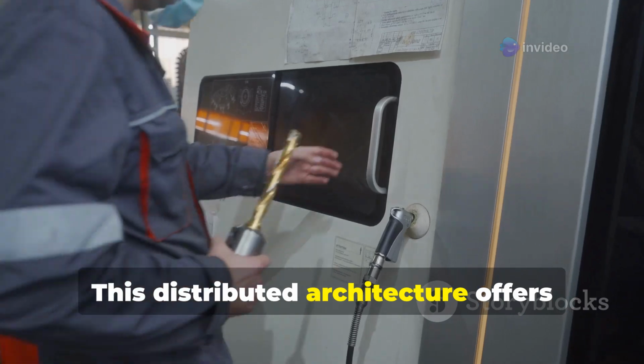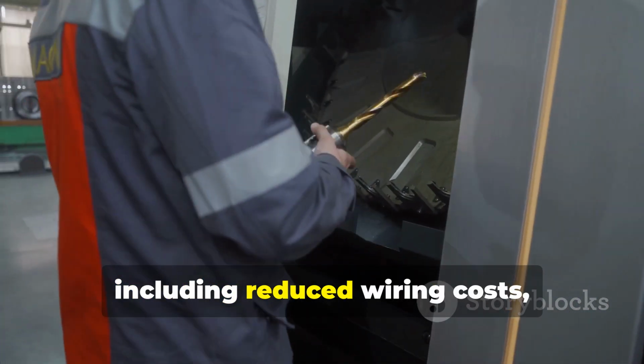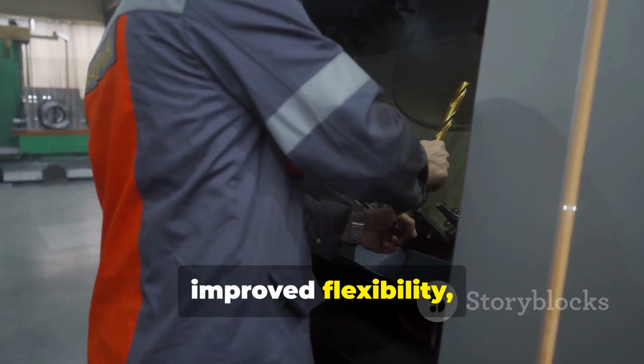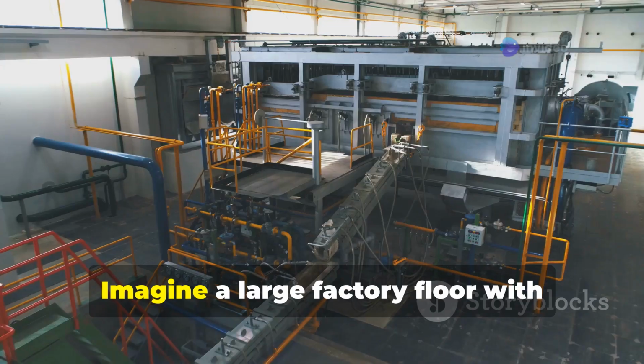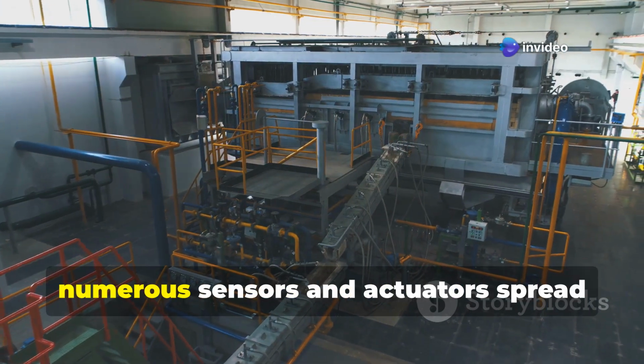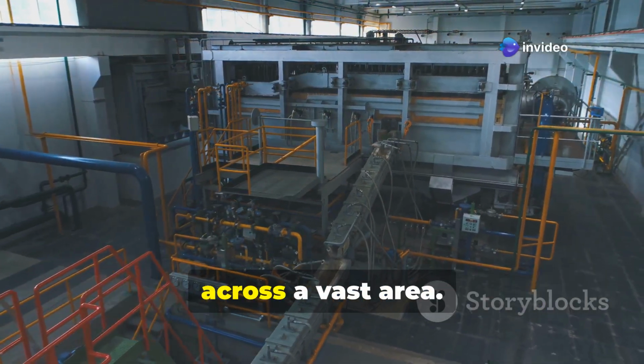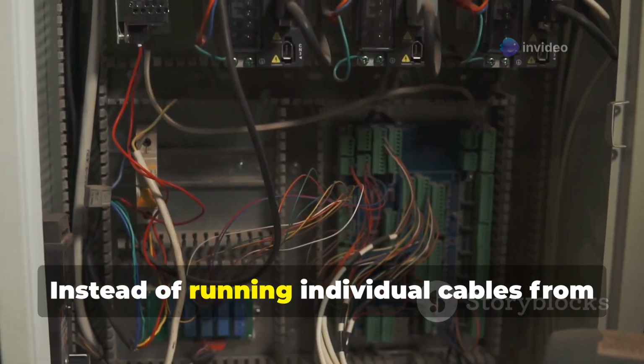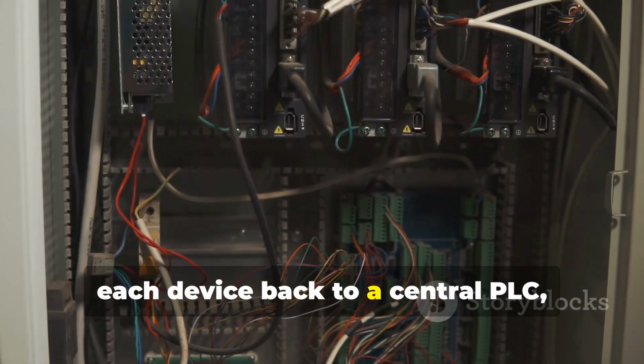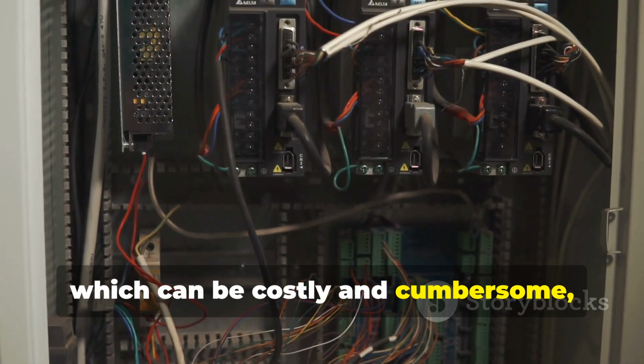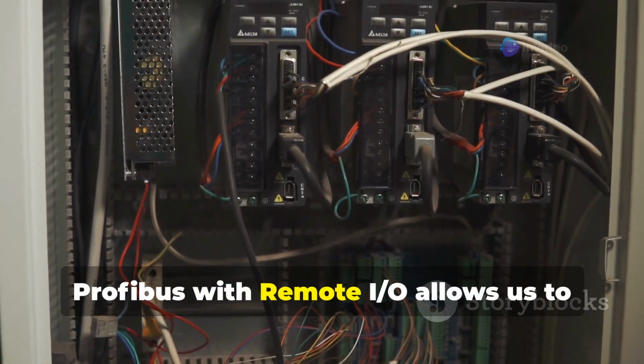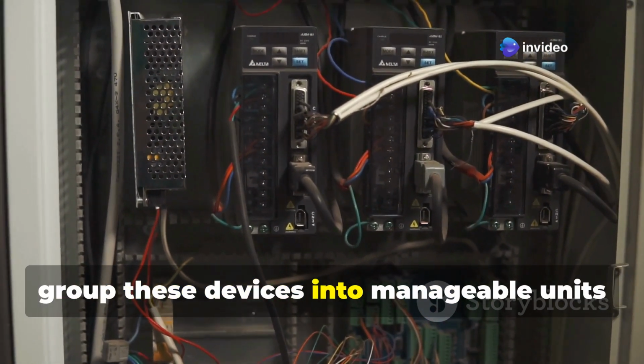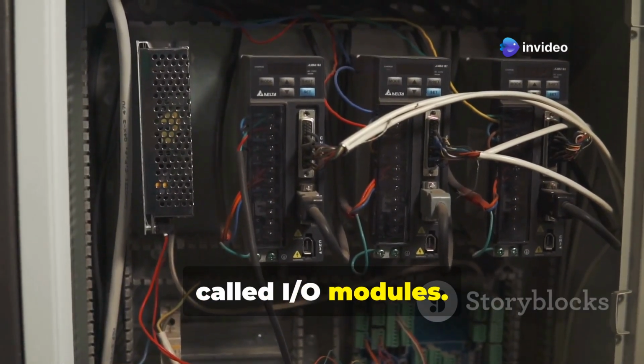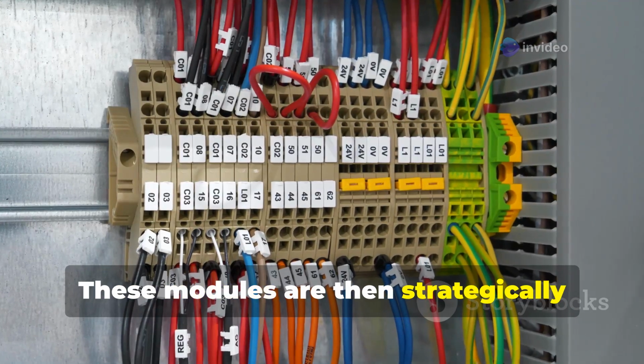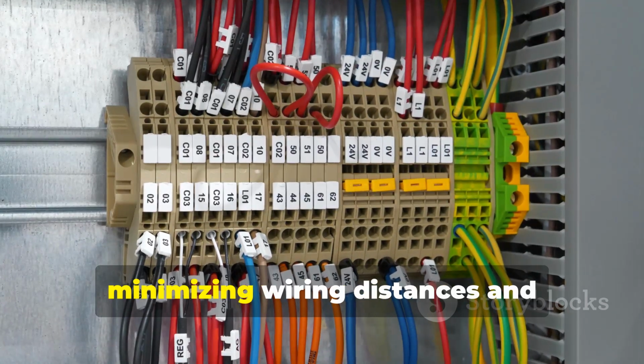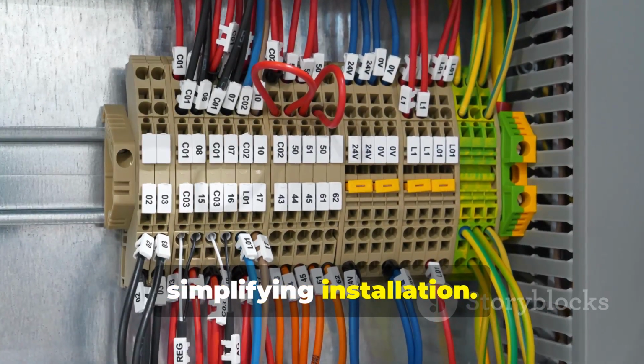This distributed architecture offers several advantages, including reduced wiring costs, improved flexibility, and enhanced diagnostics. Imagine a large factory floor with numerous sensors and actuators spread across a vast area. Instead of running individual cables from each device back to a central PLC, which can be costly and cumbersome, Profibus, with remote I/O, allows us to group these devices into manageable units called I/O modules. These modules are then strategically placed near the field devices, minimizing wiring distances and simplifying installation.